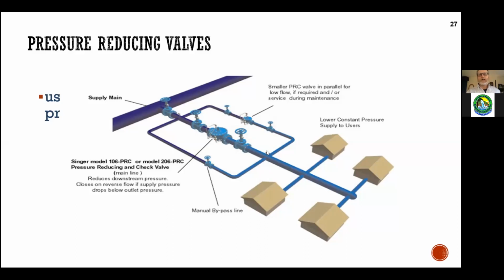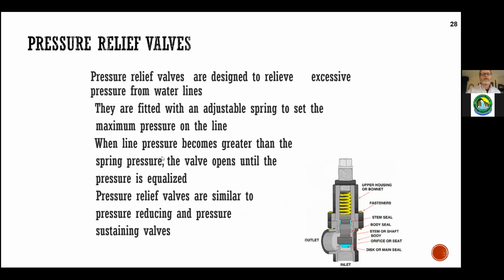And the pressure gauge below is plumbed in through the pilot so that as demand increases, this valve starts to open to fill in the need. If it's too much, then this valve will join in to supply maximum supply, including emergencies. And then as the pressure starts to climb because we've got more water going in than they're really using, this valve will close and then the second valve will close. Okay, so it's all under the umbrella of globe valve.